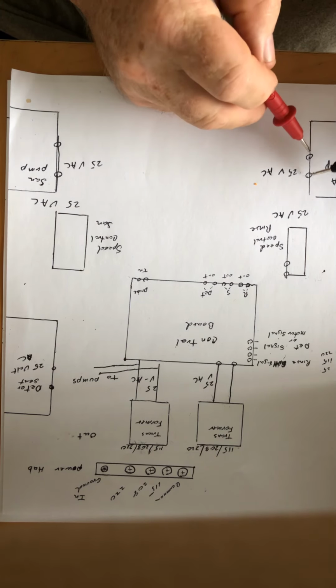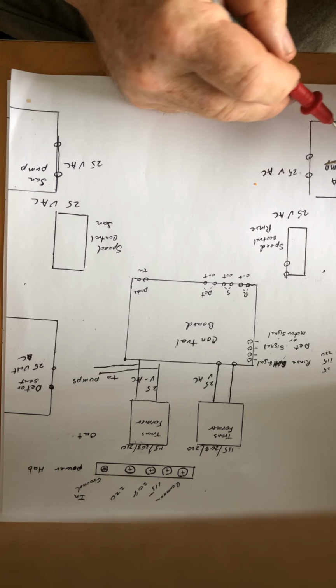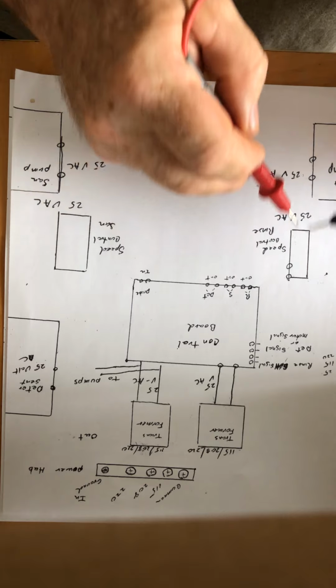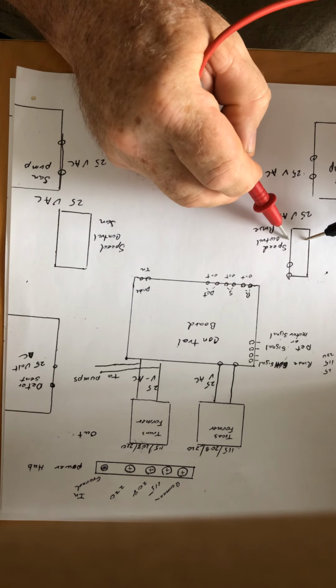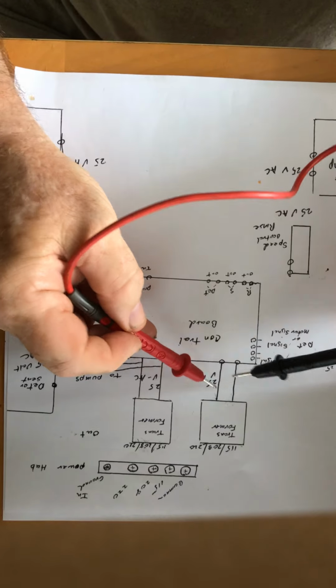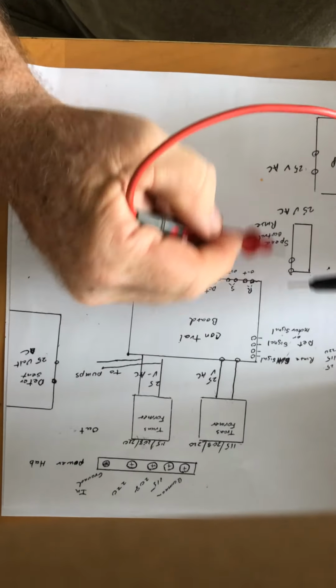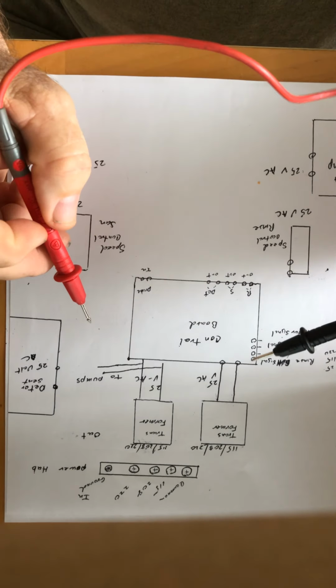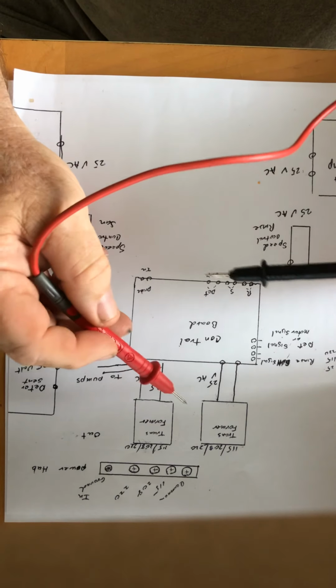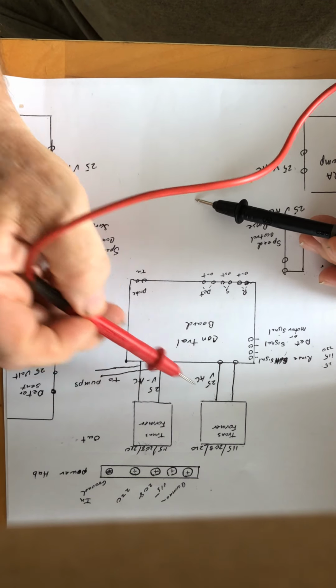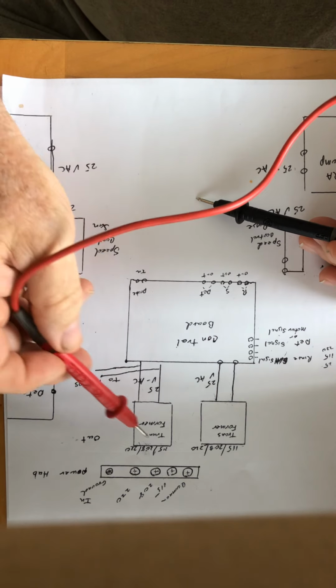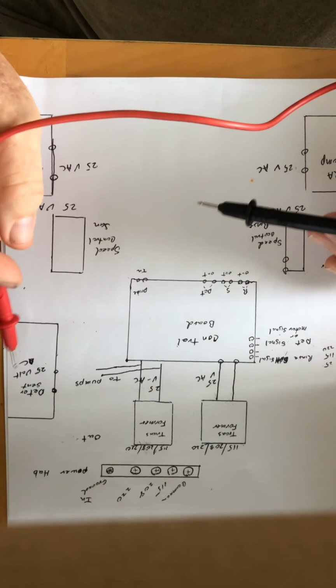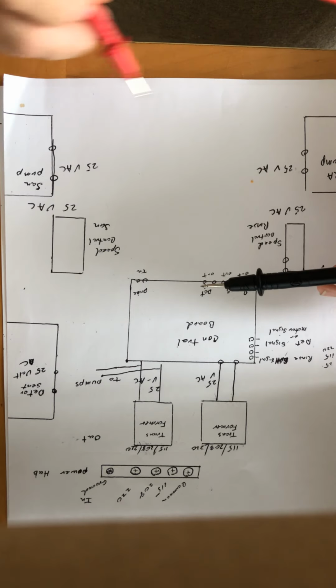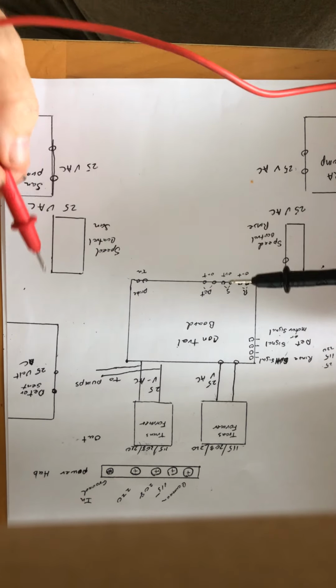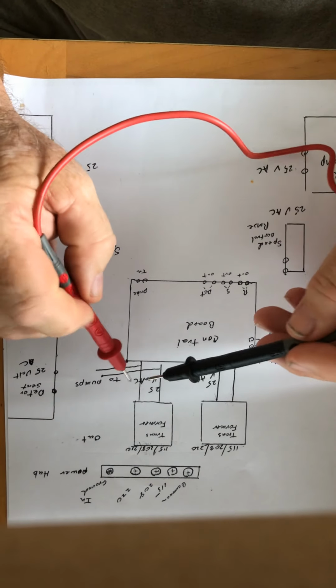If your pump's not spinning and you got voltage here, your pump is bad. If you got voltage here, and you have no voltage here, your speed board is bad. If you have power here and no power here, then no power here, you know your transformer is bad. That's how you can see what's working, what's not. Most units also use one transformer for their main computer board, another transformer for the accessories. It could be the detergent, the sanitizer pump, or the rinse aid pump, or the speed controls, or the prime buttons, but it's still all 25 volts.